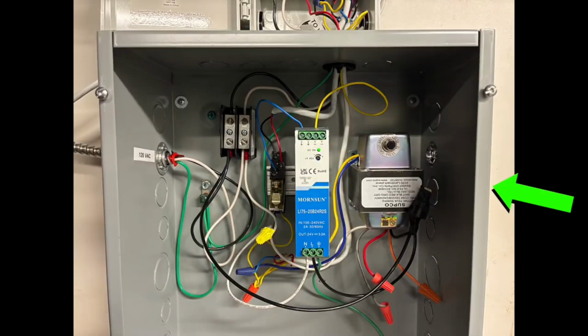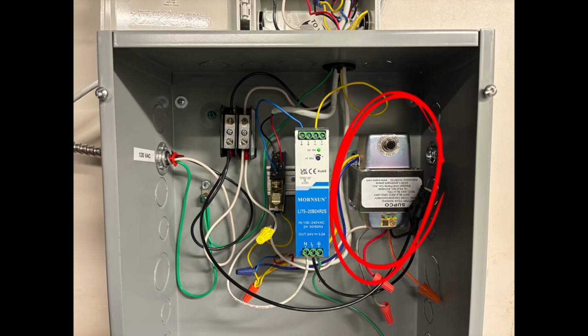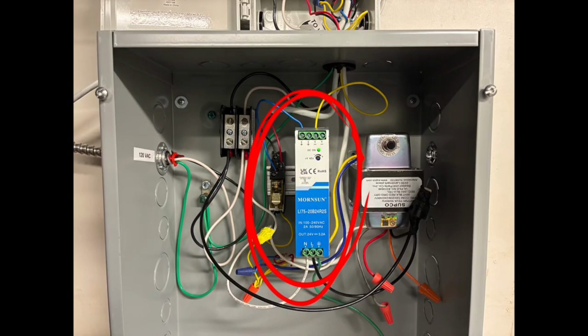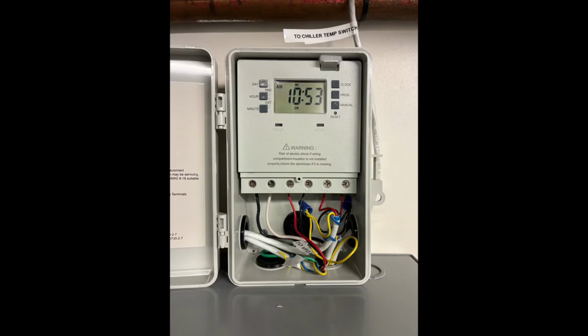So I simply mounted this enclosure that we already had as a spare stock in our facility, mounted to the wall. So you've got 120 volts coming in the left-hand side, and you can see our 24 volt wires go out the top into our programmable digital timer. See our step-down transformer. There's our power supply, our IDEC relay. And then here's that programmable digital timer. You can see the 24 volt wires or shielded wires going out the left-hand side there to the VFDs. And then there's one going out the top there that's going up to the roof to the chiller temperature switch and provides power to the temperature switch.